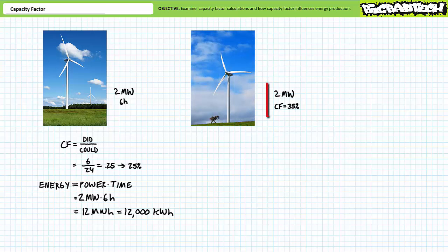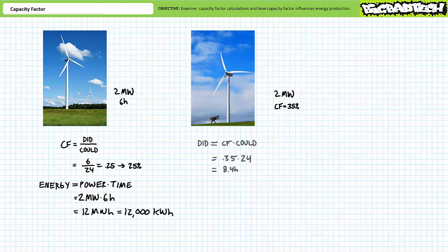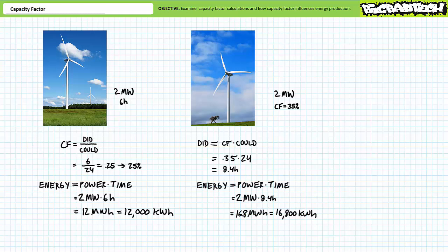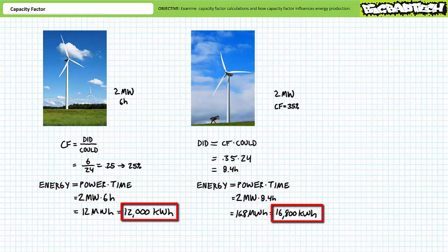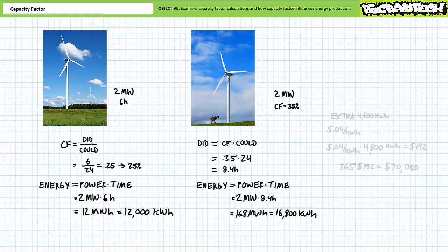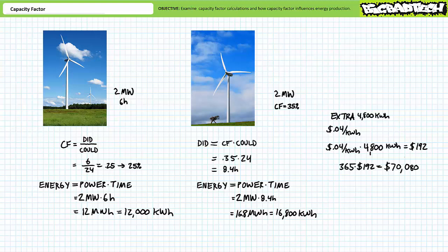Consider however if this same turbine was installed in a slightly windier area with an increased capacity factor of 35%. An algebraic rearrangement of the capacity factor formula suggests this turbine is typically at full production for 35% of 24 hours or 8.4 hours. Again if energy is power times time, this turbine with a higher capacity factor typically produces 2 megawatts times 8.4 hours or 16.8 megawatt hours or 16,800 kilowatt hours of energy. Compare and contrast the energy output of the two similarly related turbines operating in regions with different capacity factors. The higher capacity factor turbine can be expected to produce 4,800 more kilowatt hours every day than one in a less windy area.